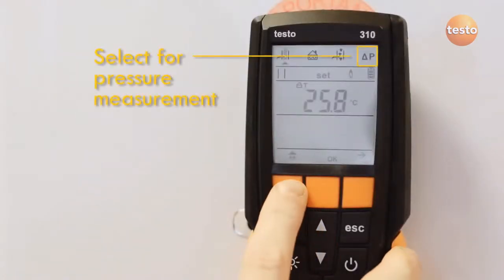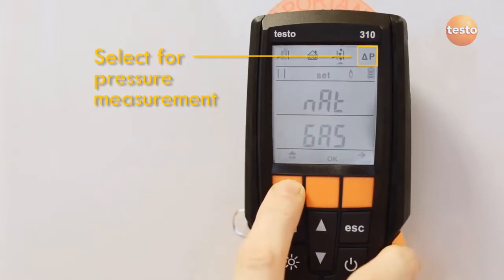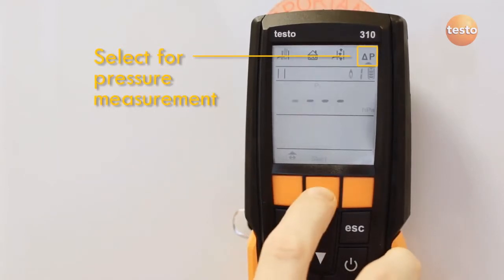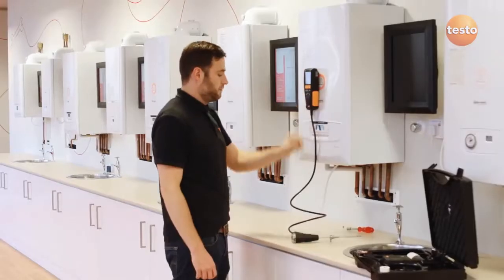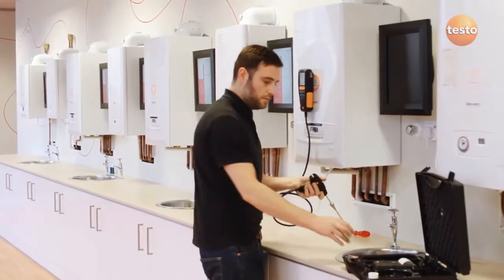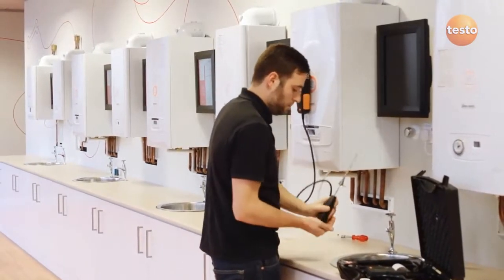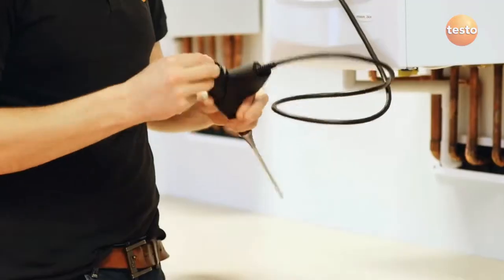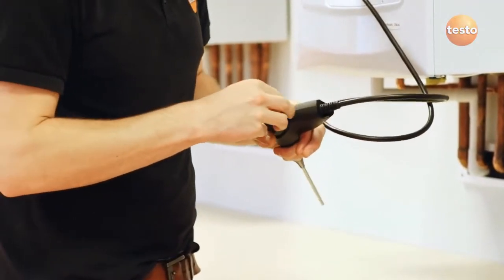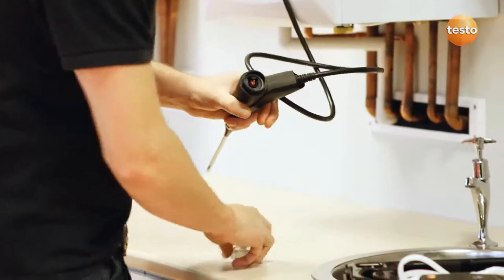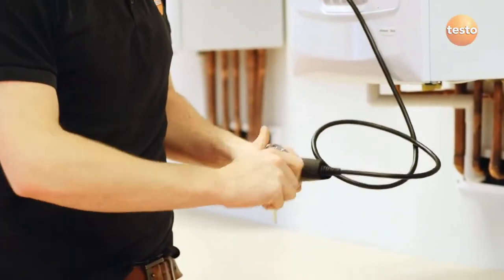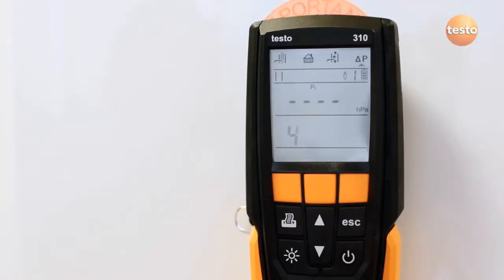To measure gas pressure, select the pressure test mode, which causes the 310 to remind you to fit the pressure plug in the probe. This seals off the gas path to allow pressure to be measured. Remove the filter and put the orange plug into the hole in the center of the probe handle. Once the plug is in place, press start to zero the pressure sensor before connecting the probe to the gas supply with the silicone hose.